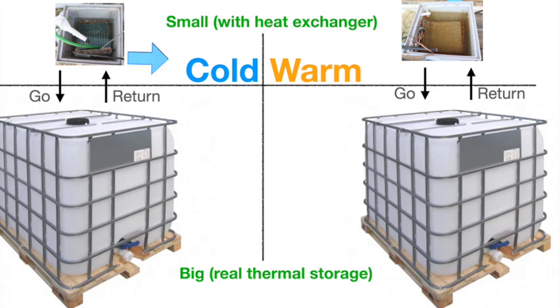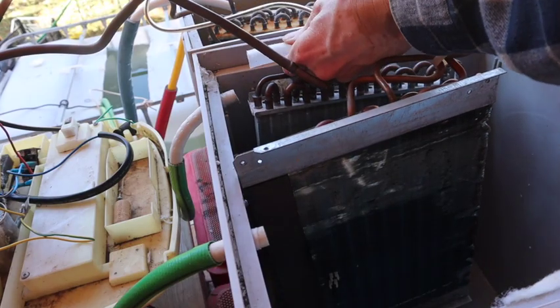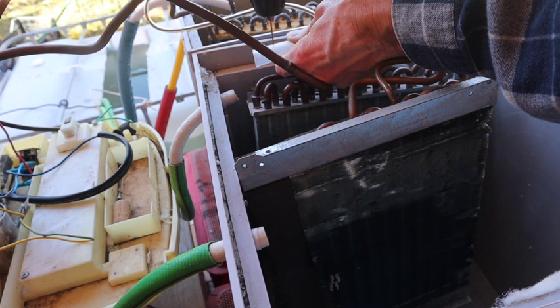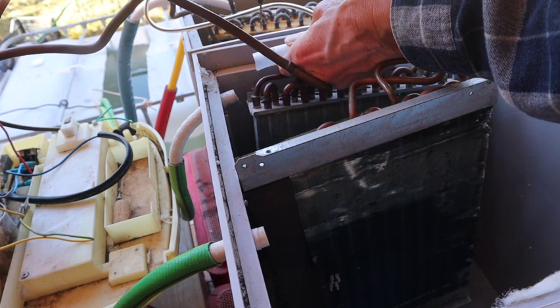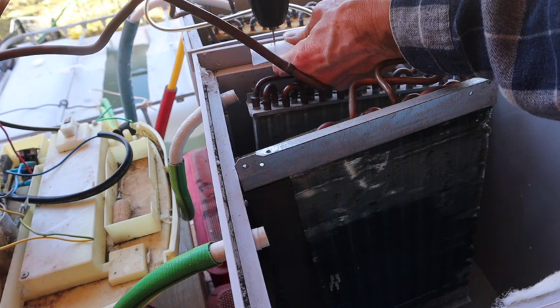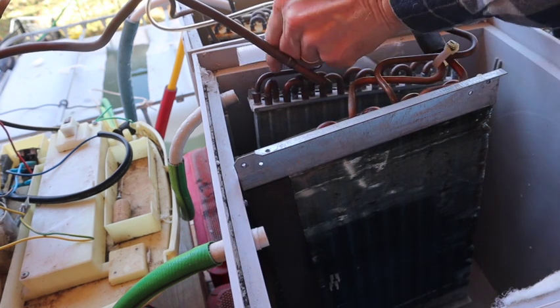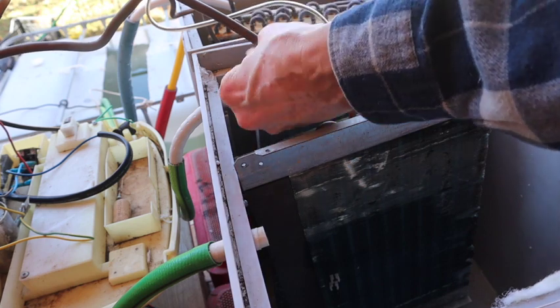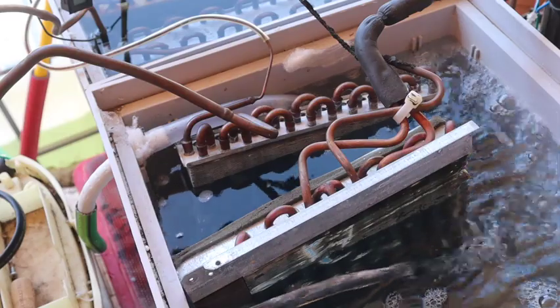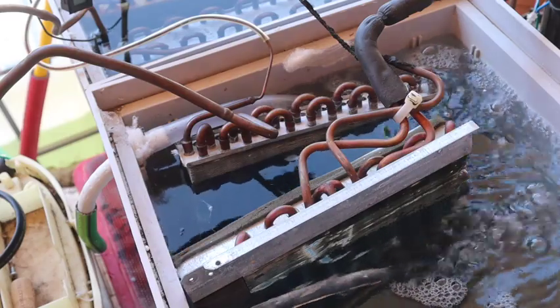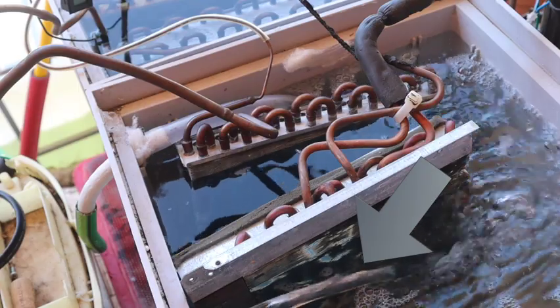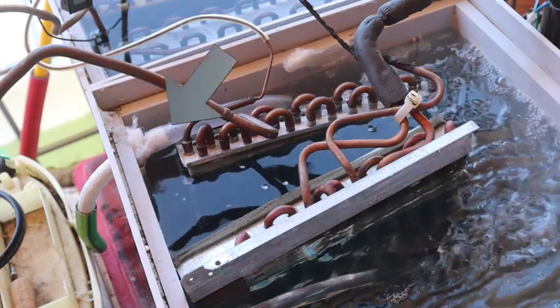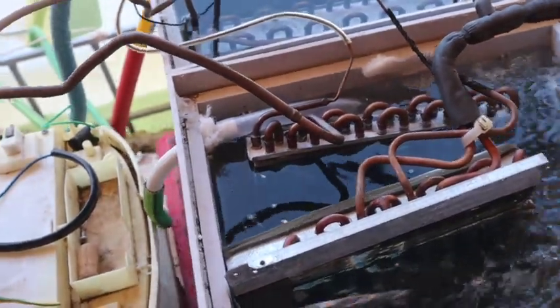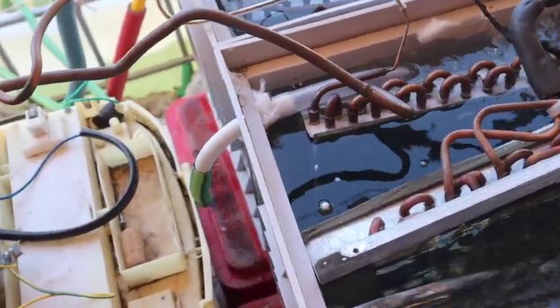Discharge water from the bottom of the cold water box to the big tank and discharge it at its bottom to have maximum stratification. I found a trick to suck water from the bottom of the water box without draining the whole water box. It works by drawing in false air as soon as the water level goes below a certain level, by making a few holes in the extraction tube so that it will stop to draw water from the hose that goes until the bottom. But as soon as the supply tube fills the water box up again, this air entrance will be covered and the water will continue to be taken from the bottom. Also here, the gravity will avoid that the water will flow over.